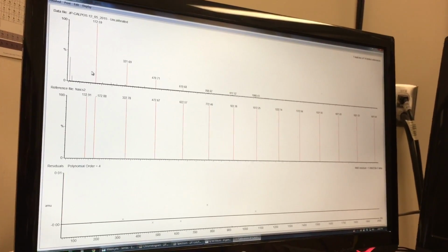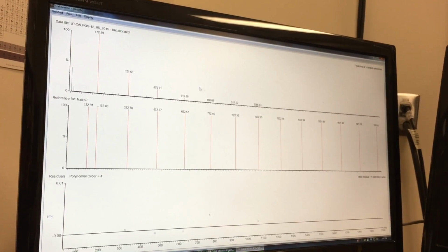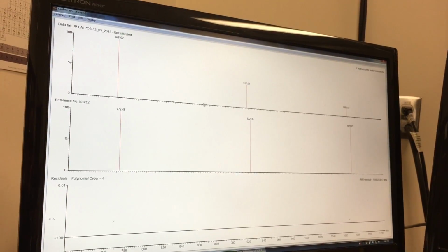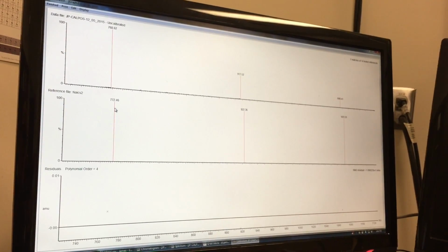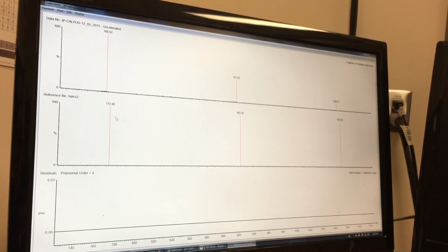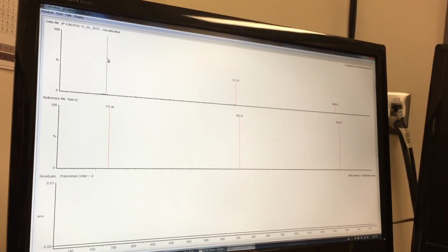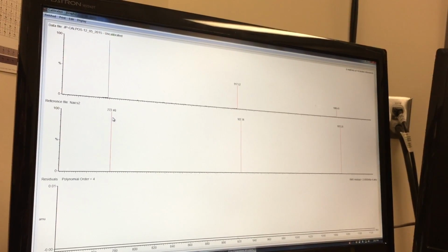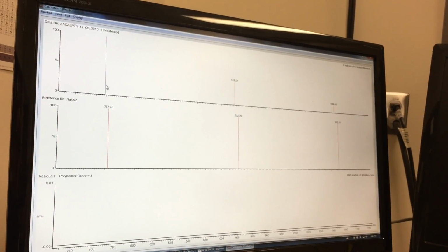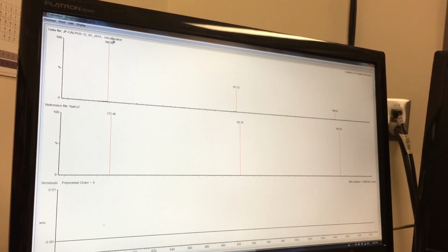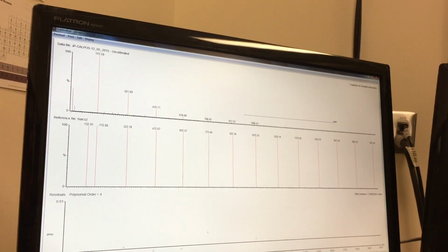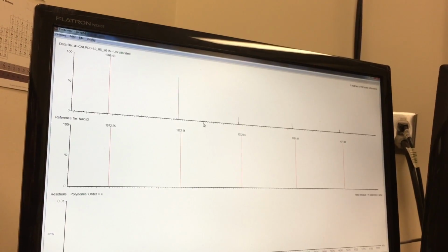Okay. So in some scenarios, not every peak will be lined up with an experimental peak. In that case, or if you want to double check that you are clicked on the correct peak, you can right click on the calculated window and then right click the corresponding peak in your experimental window. As you can see, that deselected a certain calibration peak, or you can add different peaks into your calibration curve if you so desire.